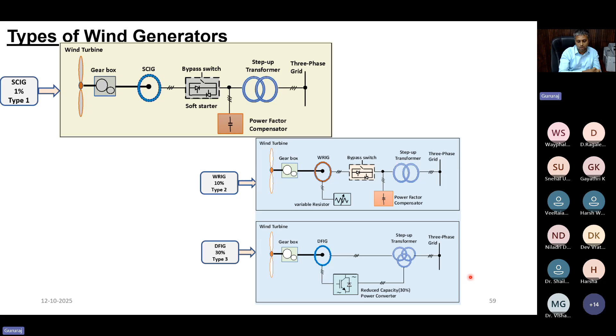So let's say it's a 6-pole induction machine, a slip ring induction machine being employed, and the synchronous speed of operation is 1000 RPM. If the wind speed is such that the rotor speed has not reached the 1000 RPM synchronous speed, at which ideally you generate power at 50 Hertz and can synchronize with the grid, and the rotor speed is much lesser, maybe 800 or 900 RPM, then there is a positive slip. Slip could be 0.1 or 0.2 or whatever. In that case, you need some assistance from the rotor side, so that you make it look like 50 Hertz power and then feed it to the grid.